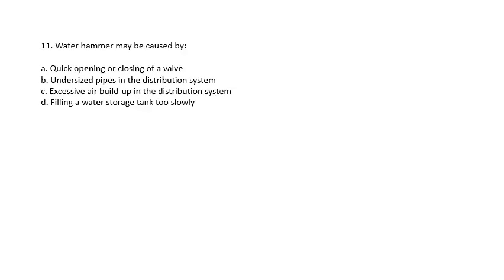Question 11: Water hammer may be caused by quick opening or closing of a valve, undersized pipes in the distribution system, excessive air buildup in the distribution system, or filling a water storage tank too slowly. The answer is quick opening or closing of a valve.